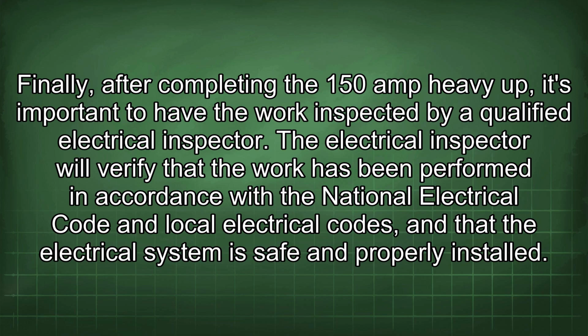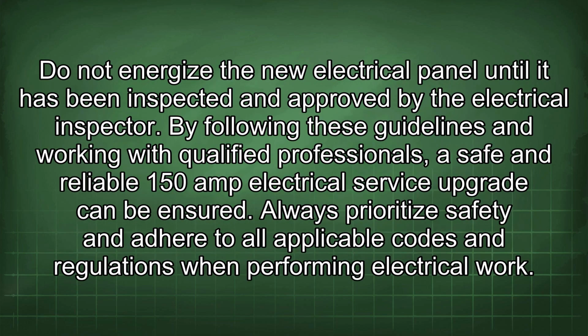heavy up, it's important to have the work inspected by a qualified electrical inspector. The electrical inspector will verify that the work has been performed in accordance with the National Electrical Code and local electrical codes, and that the electrical system is safe and properly installed. Do not energize the new electrical panel until it has been inspected and approved by the electrical inspector.